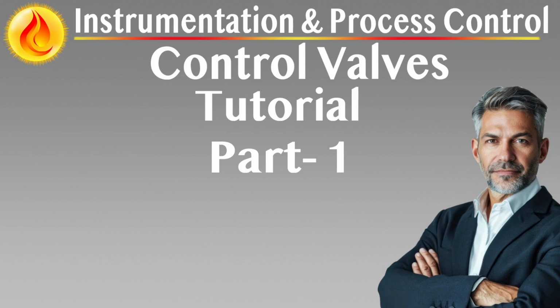Seat leakage and flow direction. Emergency shutoff valves must be configured for flow tending to close to ensure reliable closure under line pressure. For throttling control valves, especially those with unbalanced designs, the preferred configuration is flow tending to open to reduce instability and excessive forces near closed positions.